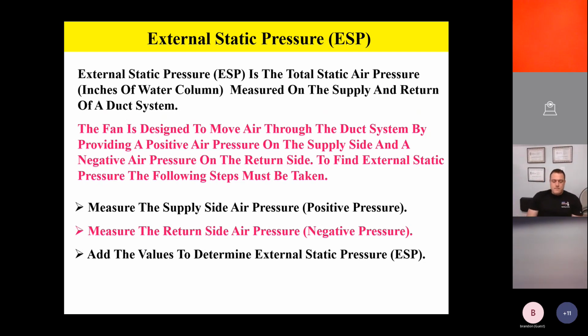Step number 2, we're going to measure the return side pressure, which is a negative pressure. And then we're going to just add those values together. Now, fellas, I want to stress something. With today's tools, sometimes you have a 2-channel digital manometer or magnehelic gauge. Some technicians like to take the supply and the return air pressure together, like on channel 1 and channel 2 of their gauges. And that's fine to do that, but I highly recommend that you take the pressures individually.